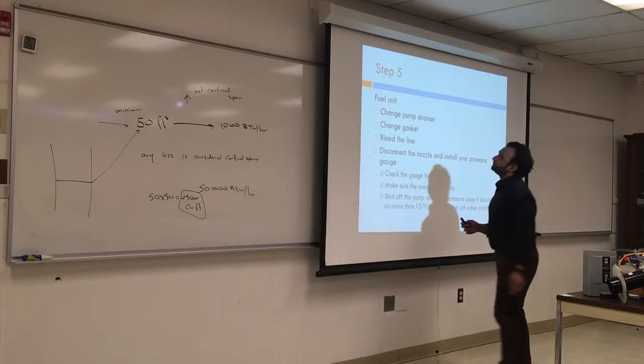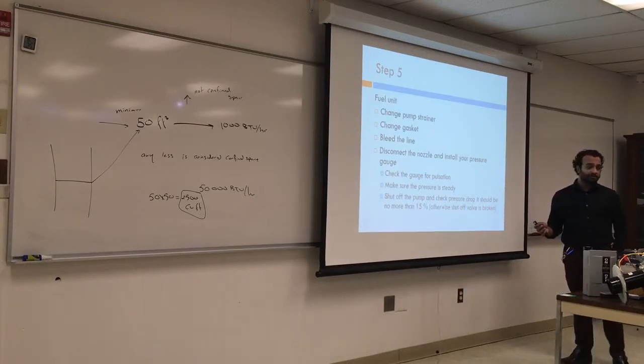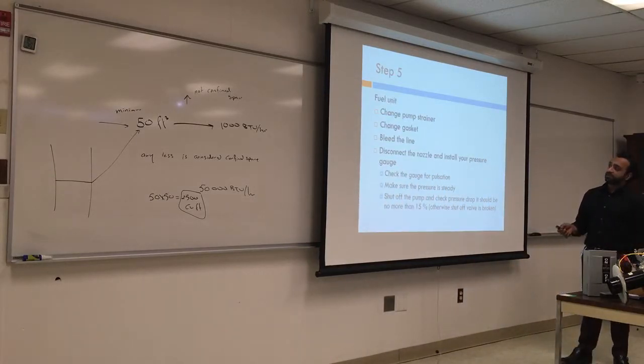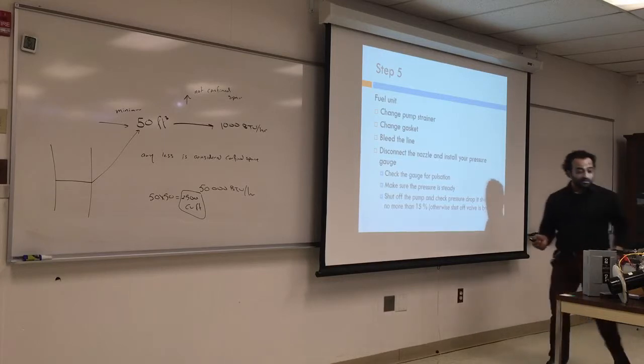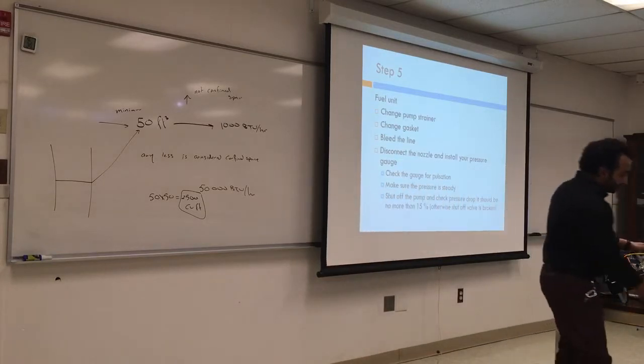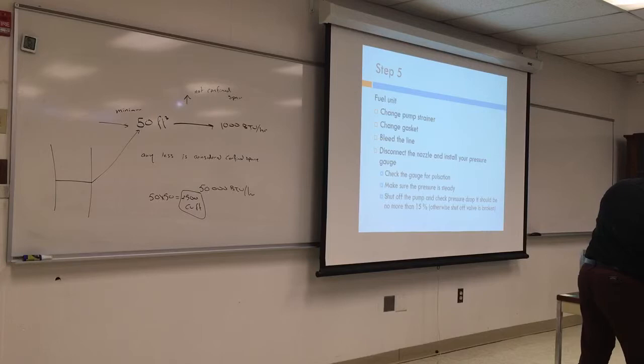The fuel unit, change the pump strainer. Some pumps have a strainer right on top of them. Change the gasket. Bleed the line. Do you know how to bleed the line? Purge line. So this is your purge line here. You purge it. So you put a hose in here and loosen it a little bit.